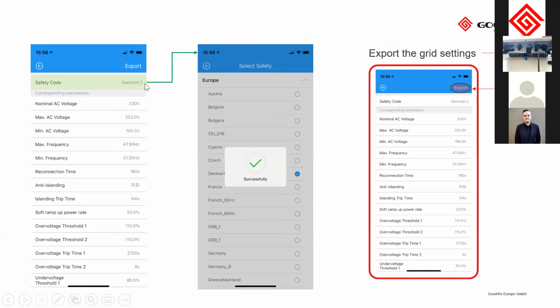When you select the safety code, in this example, it's Denmark here already added, but then you will get to another window, and then you just choose the region, if it's Europe, if it's Africa, or wherever it is, and then you choose the correct country that will have the correct grid settings. In case you don't find your country in this list, there are also some default options. So it's called 50 Hertz default and 60 Hertz default. You can choose those 2, and then you can set up specific parameters yourself.